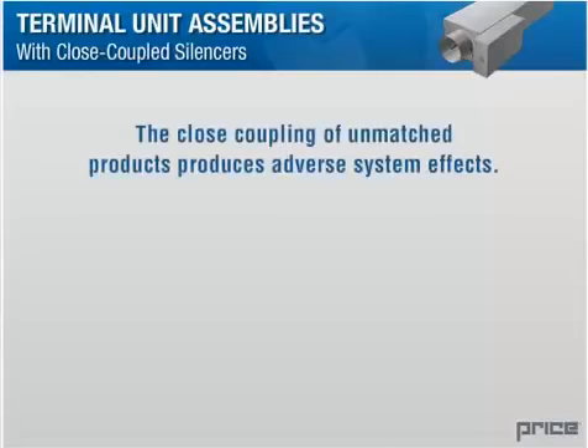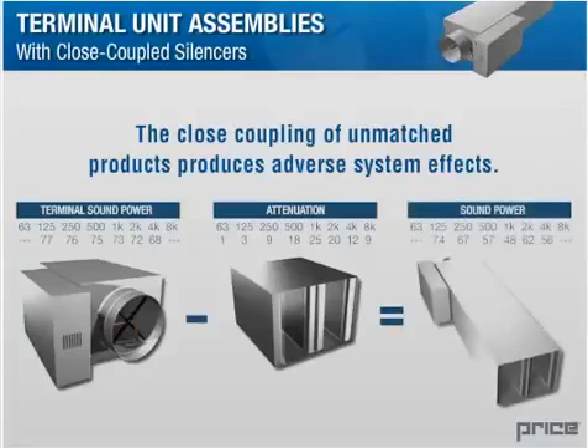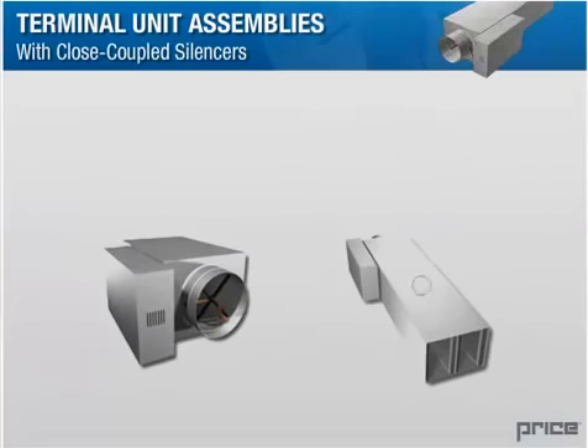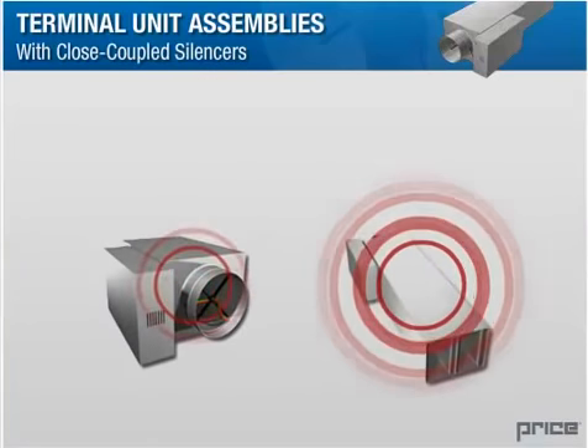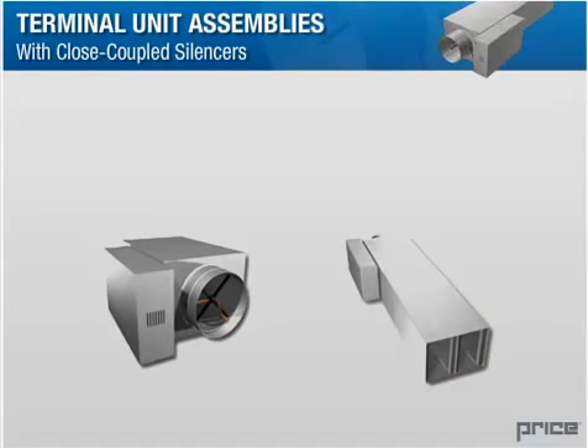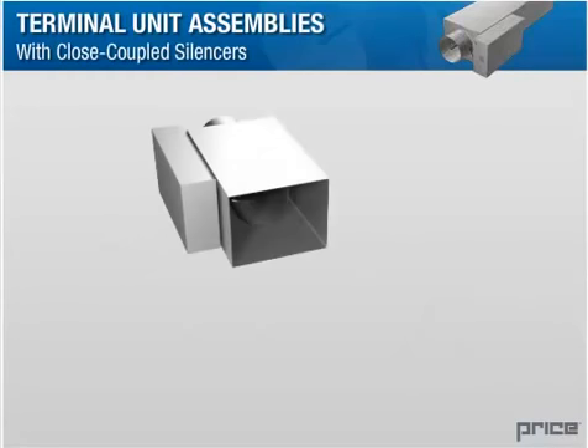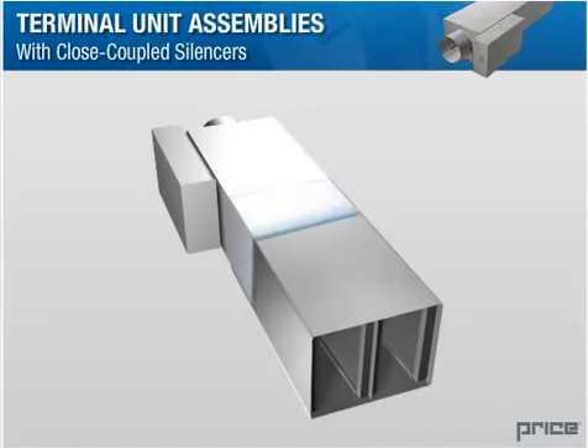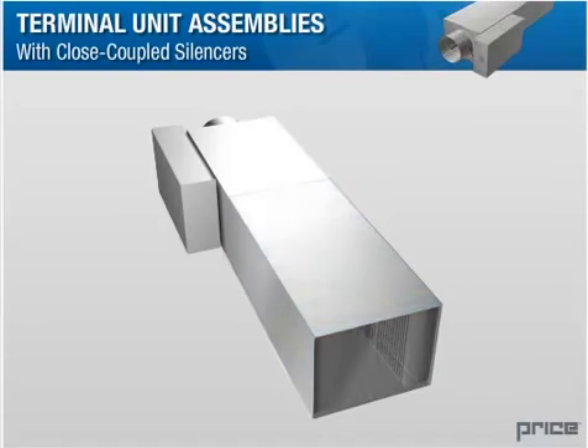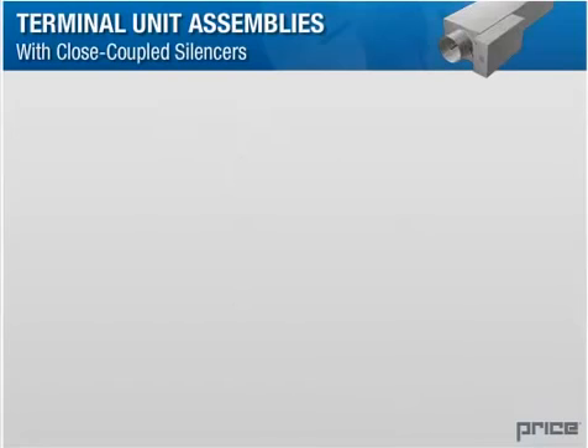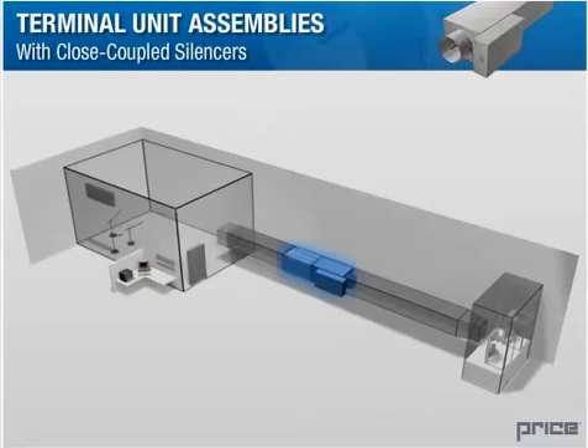Terminal unit assemblies with close-coupled silencers. We have just seen that the close coupling of unmatched products produces adverse system effects, which resulted in inaccurately predicted results, and in some cases sound levels higher than a standard terminal unit without standard silencer treatment. To solve this issue, we must take a new and innovative approach to attaining a quieter unit outside of standard configurations. One such concept is to combine terminals with specifically matched silencers in one integrated and fully tested terminal unit product. By testing the terminal and the silencer together as one assembly in accordance with the ARI 880 standard, variables associated with close coupling products from 2 different manufacturers can be eliminated.